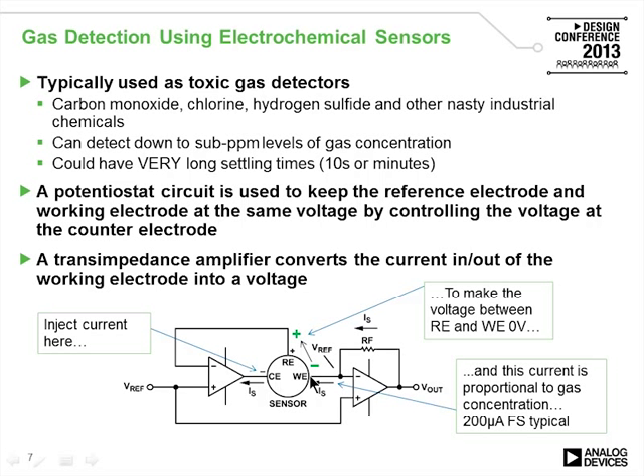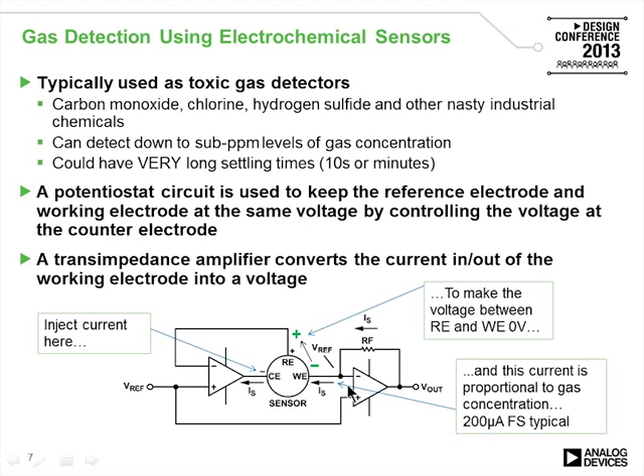This forces the reference and working electrode to zero volts. The small current that comes out of the working electrode is proportional to the level of the toxic gas — this is done via an electrochemical reaction, so the current is actually generated in the device itself. That current gets converted into voltage using a transimpedance amplifier as a current-to-voltage converter. Typically, full-scale output currents for these sensors are about 200 microamps.